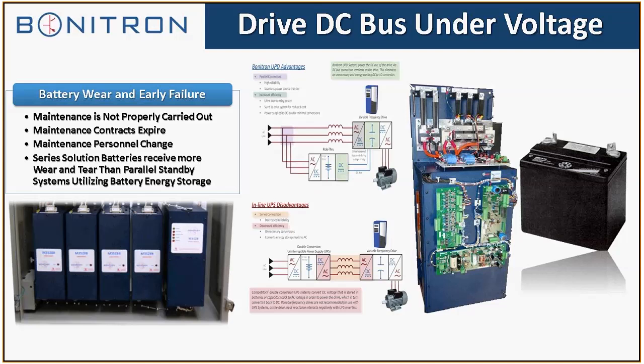And as I said, usually UPSs start at 5 minutes. You may not need 5 minutes. So we can actually size the batteries to the actual time and spec you need, so you're not stuck with overkill or much more than what you actually need.